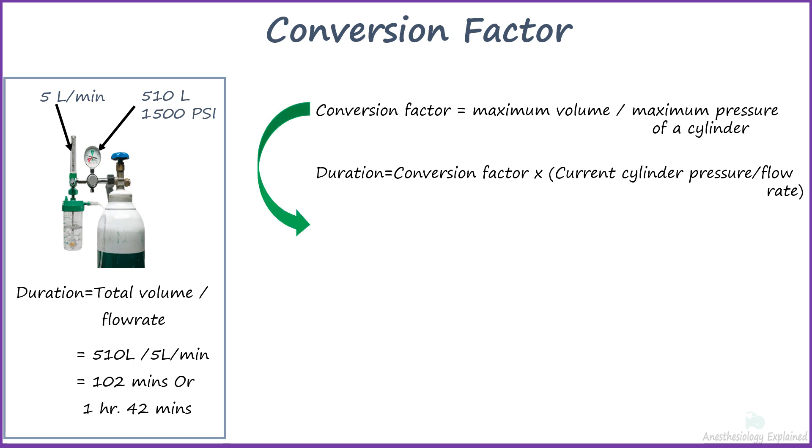First, let's calculate the conversion factor taking maximum volume of E-cylinder as 660 liters and maximum pressure or service pressure as 2000 psi. The factor we get is 0.33.